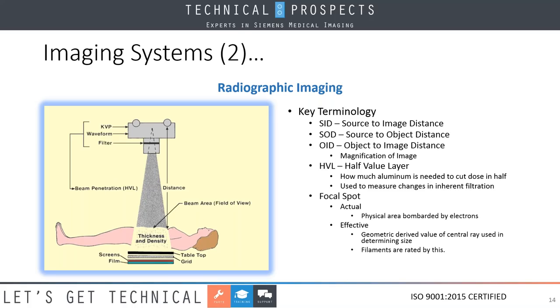Now, focal spots, there are actually two. One is called the actual focal spot, and this is the area that physically gets bombarded by the electrons in the X-ray tube. However, the one that we use is called the effective. This is a geometrically derived value of the central ray used in determining its size. This is what you see your X-ray tubes rated in. For example, if you see a 0.6 or 1.2 millimeter X-ray tube, the 0.6 is the size of the small filament and the 1.2 is the size of the large filament.